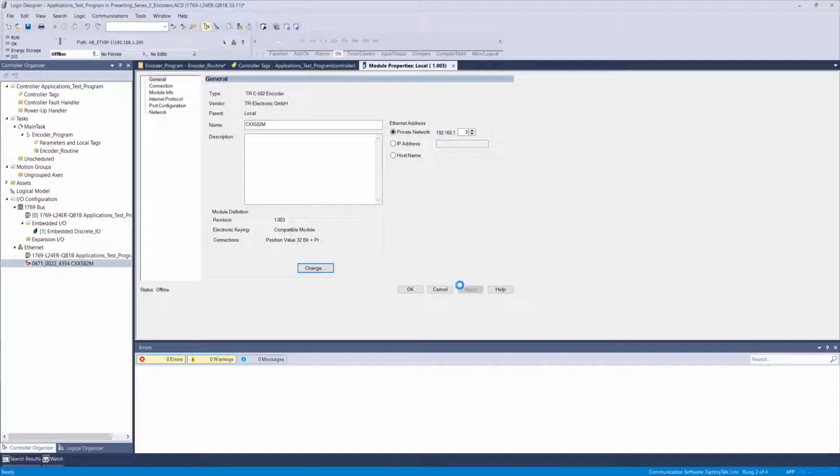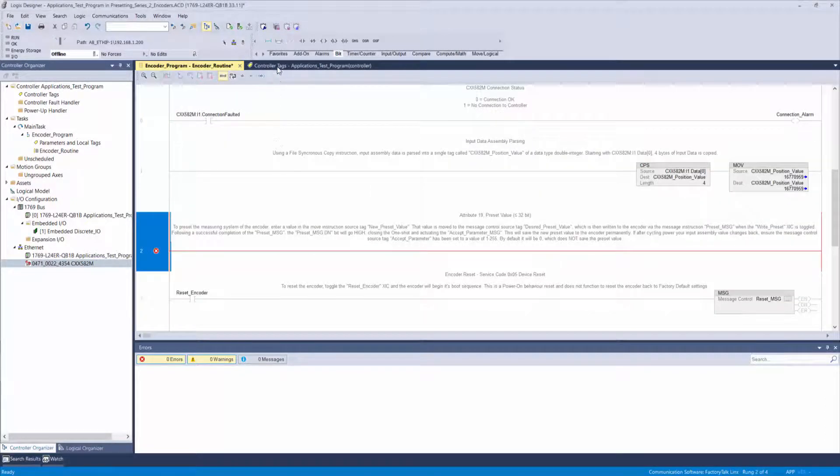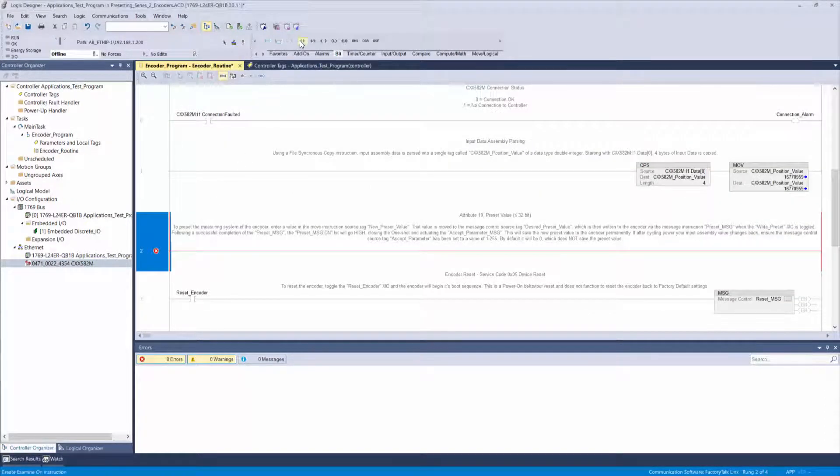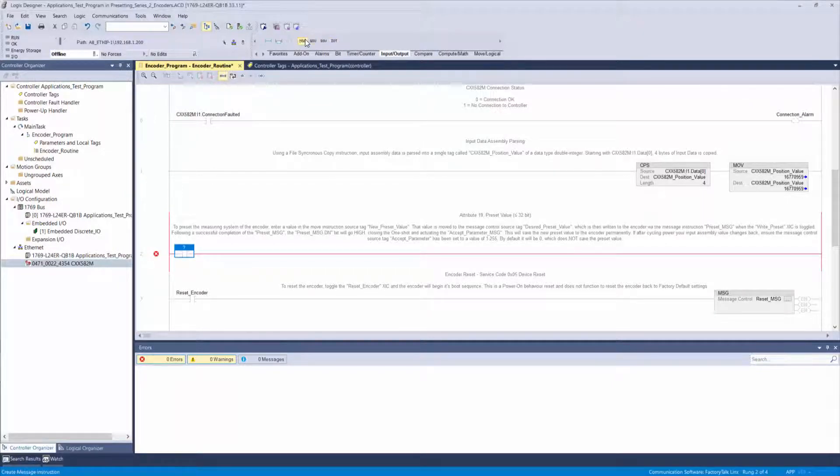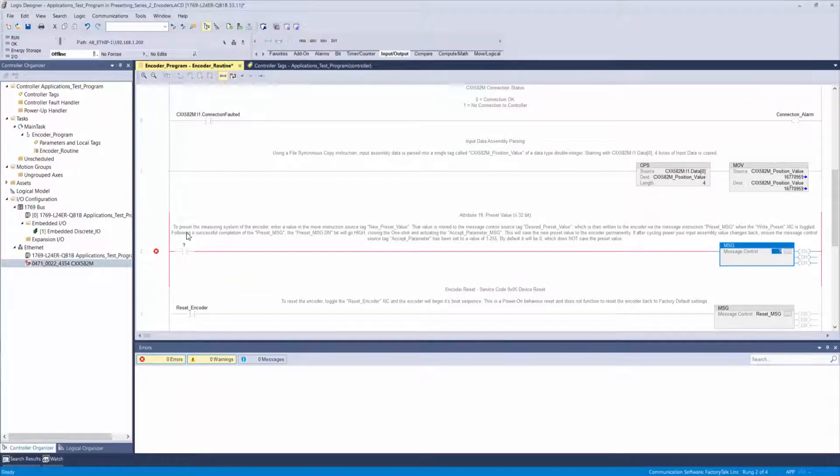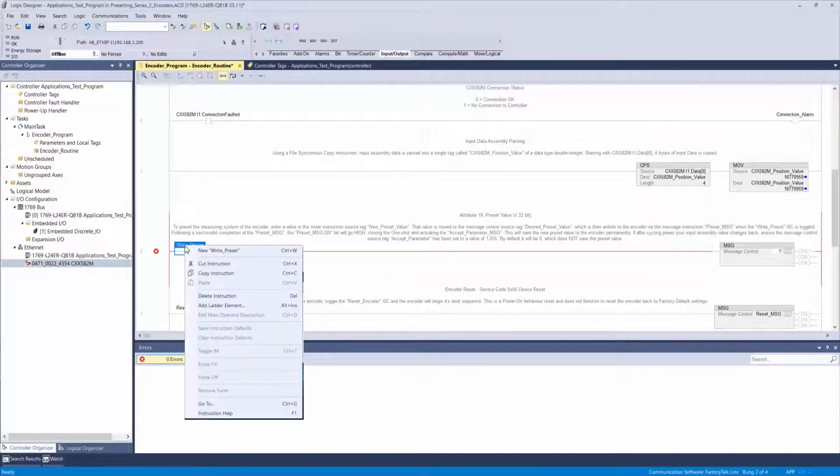Go to your ladder logic routine window and start by dragging in an empty rung. Add an XIC input instruction followed by a message instruction. Double-click the question mark above the XIC and type write preset. Hit enter, then right-click and select new write preset.